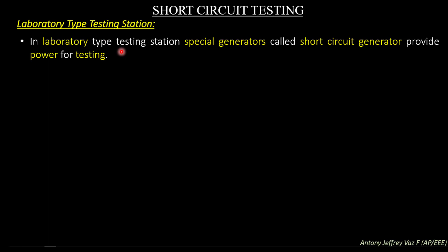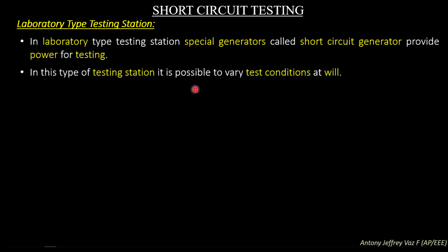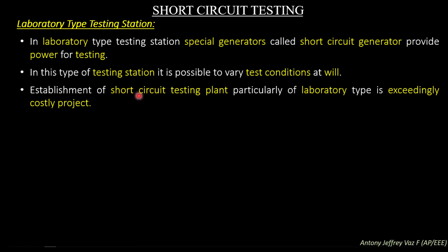In a laboratory type testing station, special generators called short circuit generators provide power for testing — a separate generator set is available for testing the circuit breaker. In this type of testing station it is possible to vary test conditions at will, so developers and researchers can test the circuit breaker according to design parameters. However, establishment of a short circuit testing plant of laboratory type is an extremely costly project.